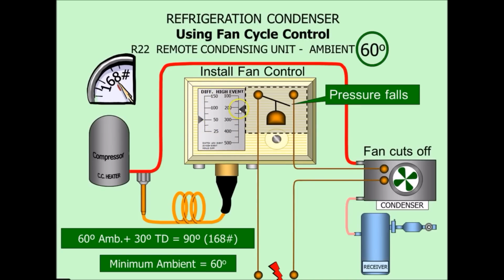So let's call this 210 at this point. So at 210 PSIG, this pressure switch will close, and anything above 210 is going to run the condenser fan motor. So 210 and above, switch closes, condenser fan comes on. Then there is a differential of 50. So if you take 210 and you subtract the differential of 50, that's 160 PSIG. And this is where the fan cuts out. So at 160 PSIG and below, this switch breaks and the condenser fan shuts off.